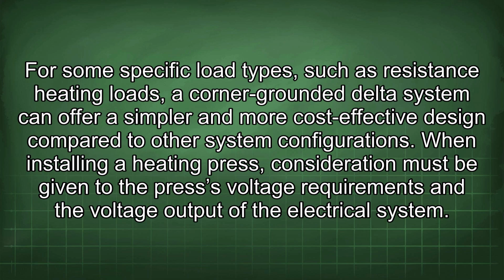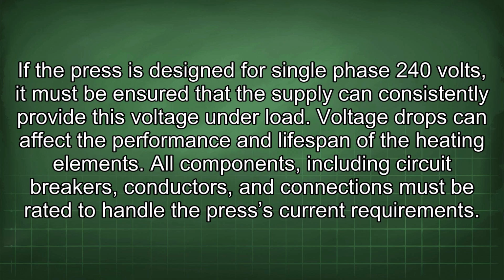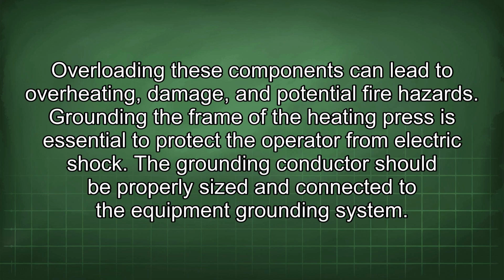When installing a heating press, consideration must be given to the press's voltage requirements and the voltage output of the electrical system. If the press is designed for single-phase 240 volts, it must be ensured that the supply can consistently provide this voltage under load. Voltage drops can affect the performance and lifespan of the heating elements. All components, including circuit breakers, conductors, and connections, must be rated to handle the press's current requirements. Overloading these components can lead to overheating, damage, and potential fire hazards.